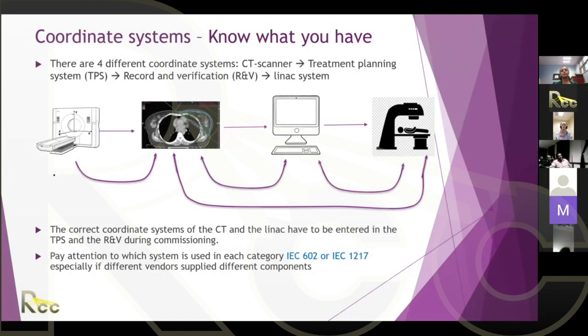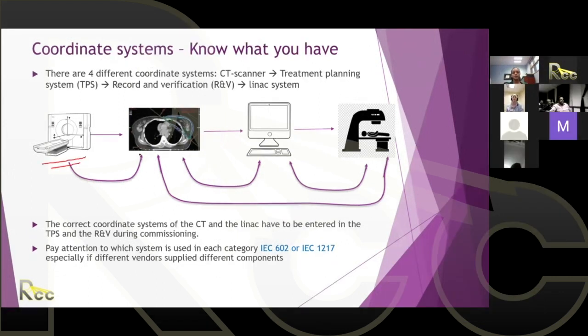You have the CT scanner, the treatment planning system, the record and verification system, and your LINAC. In most cases, they're from the same vendor, whether it's all Varian or all Elekta, for example. But for sure, your CT scanner is different - it can be Philips, Siemens, GE, or Toshiba. Or in other situations, you would have a different system from different vendors. Whether they are from the same vendor or different vendors, it's very important that the coordinate system is defined correctly.